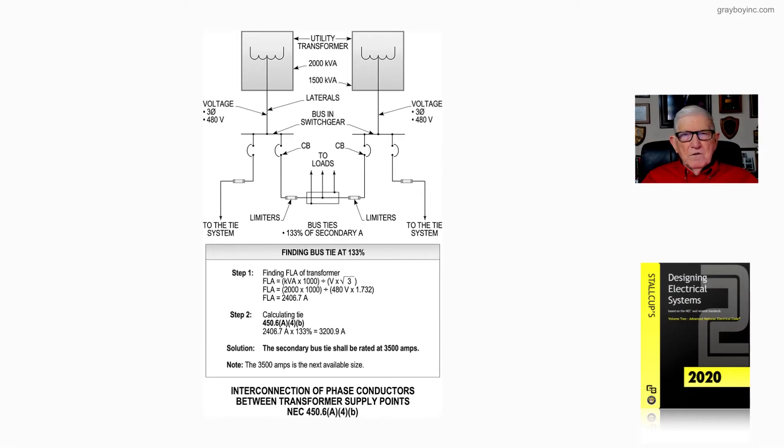Now this figure 20-17 covers the requirements of section 450.6(A)(4)(b). That actually deals with the interconnection of phase conductors between the transformer supply points, again in accordance with NEC 450.6(A)(4)(b). Now notice reviewing the illustration.